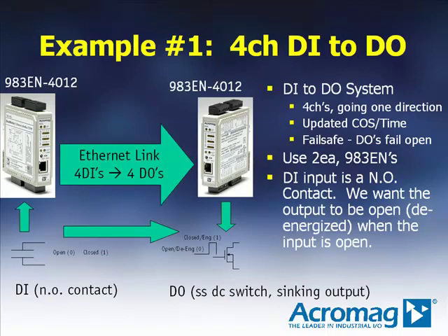The next two slides will illustrate a simple 4-channel discrete input to discrete output I/O system. The requirements are simple: four normally open discrete inputs are to be mirrored as four normally open discrete outputs. We want updates to be based on change of state and time so quick momentary closures will be captured. And in the event of network communications failure or power loss, we'll want the discrete output switch to remain open.